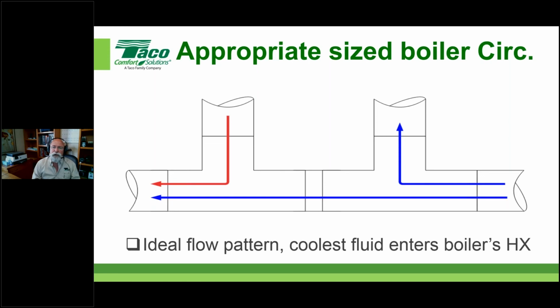If you're looking at this with that understanding, you'll surmise that if I've got water going up here and water going this direction, blending back in here, then this GPM is going to be equal to or slightly less than this GPM, and we're just splitting the flow. The idea is I don't have any of this heated water coming back across the top and coming in here. So in a primary secondary configuration, this is the ideal flow pattern. We'll give it a thumbs up.